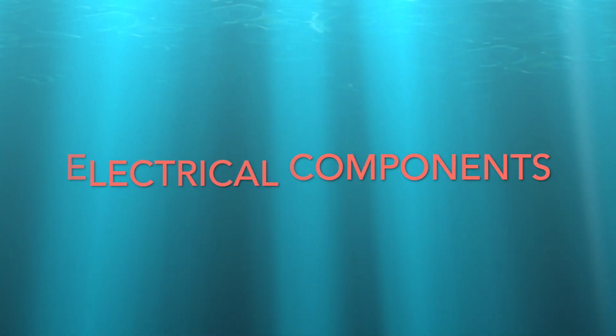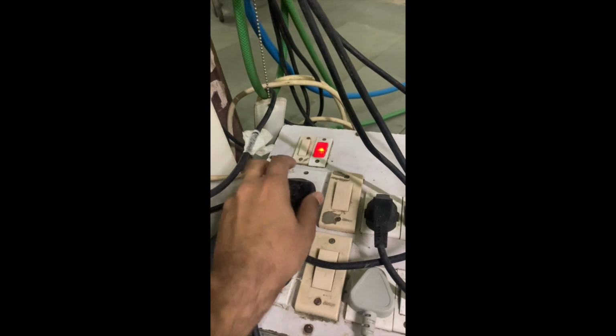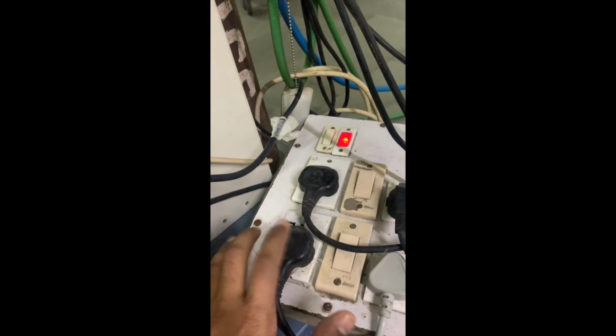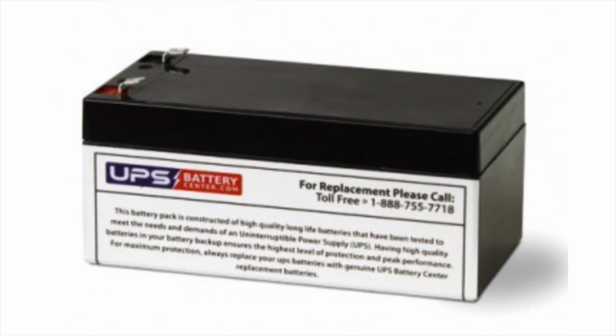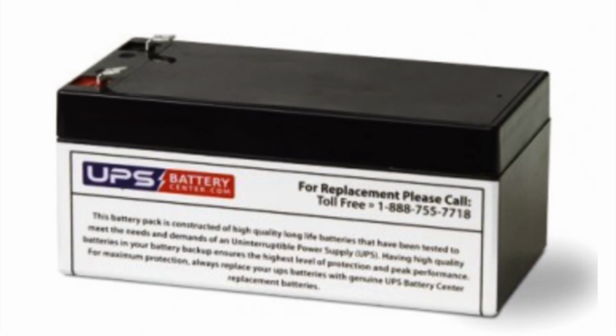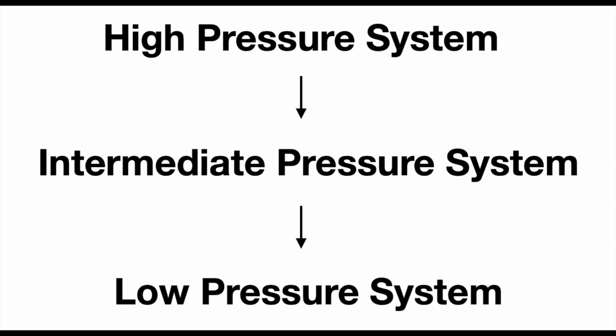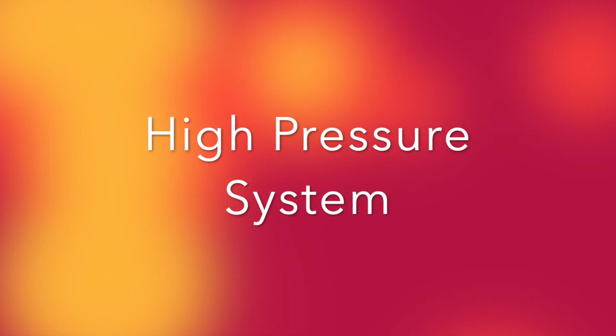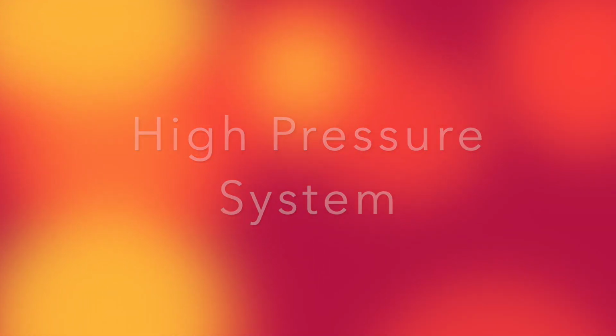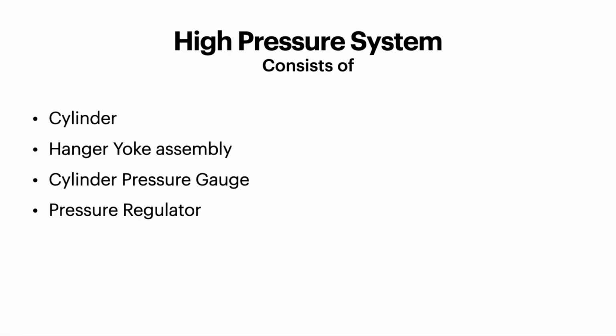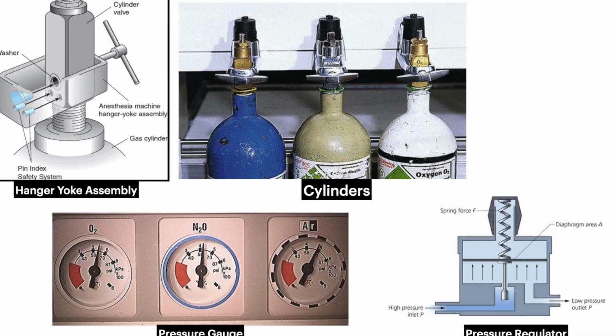In the electrical components, check for proper connection of the power outlets and ensure adequate battery backup is present. The pneumatic component of the machine will be checked in this order, beginning with the high pressure system, which consists of the cylinder, hanger yoke assembly, cylinder pressure gauge and pressure regulator.